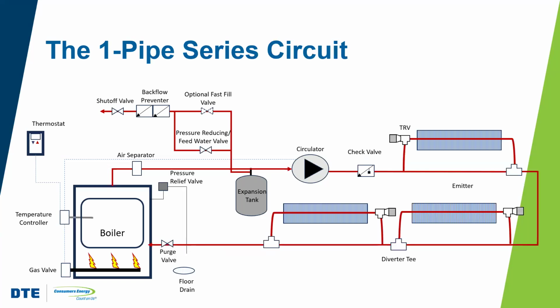So a slight change to this circuit is what we call a one pipe series arrangement. And here you can see that we've got a little bit of branch circuiting, right? So now you don't have just this one set of pipe here with all of the emitters on that, they actually have little branches off, right? There's a T, right? And then there's a valve there. So this is still a simple and low cost system, but now we've got some valves, so we can regulate, we can control, right? We can zone. We can even have emitters that are different sizes if we want, right?